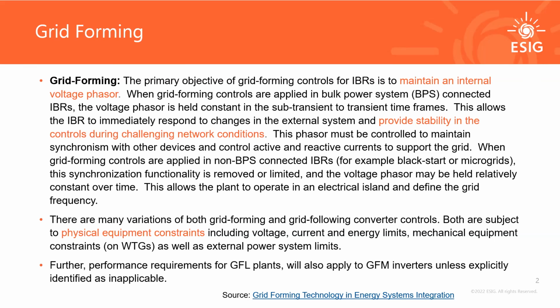I was talking to people here during the workshop, and the first thing that comes up is that there's no common understanding of what grid forming means. Looking at the requirements I've analyzed, I think there is a core agreement of what grid forming is: holding voltage in the subtransient transient timeframe, inverter-based resources holding voltage constant and then injecting current depending on what's happening on the system. I think it's not so dissimilar to how generators also differ from one another depending on what kind of functionality is there.